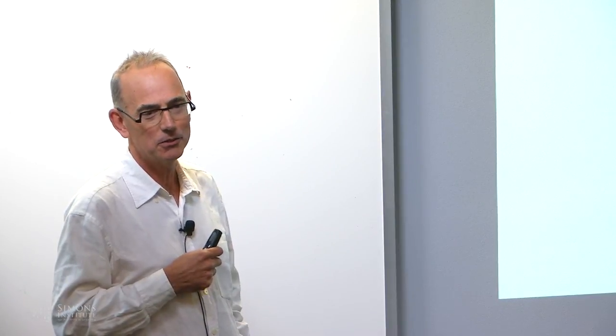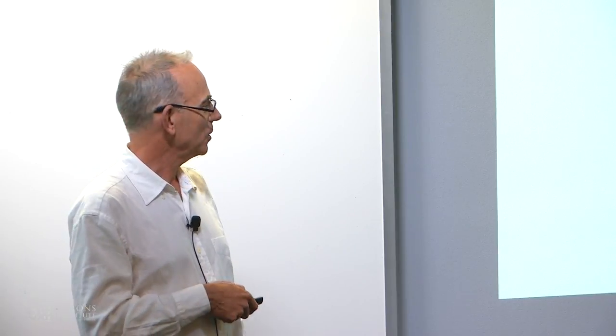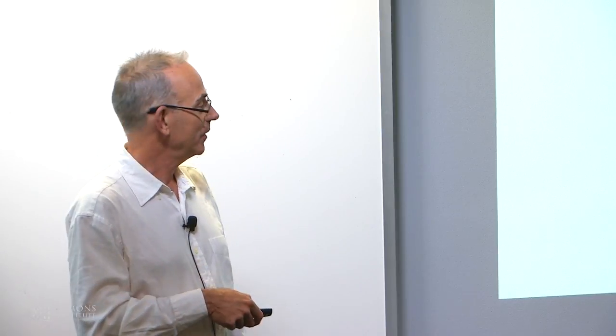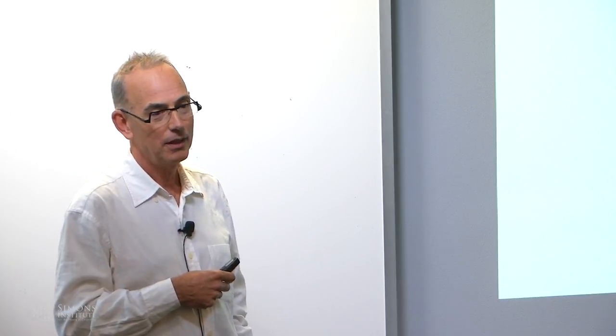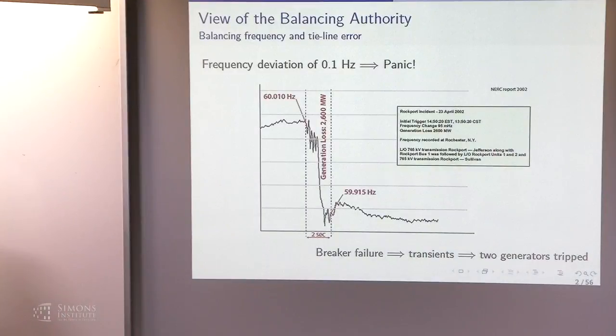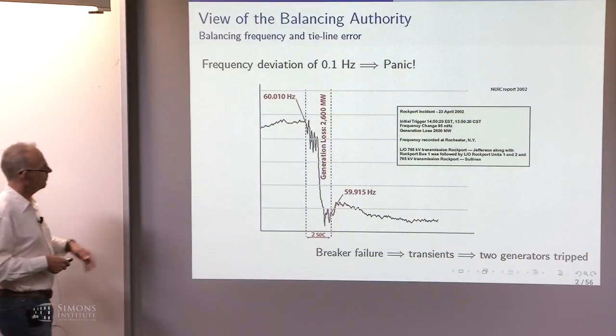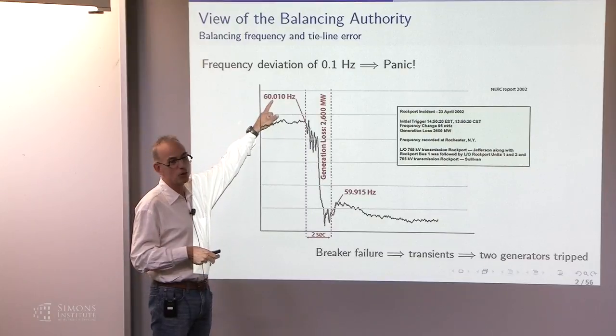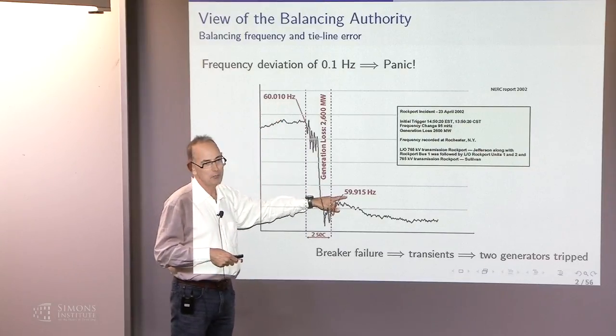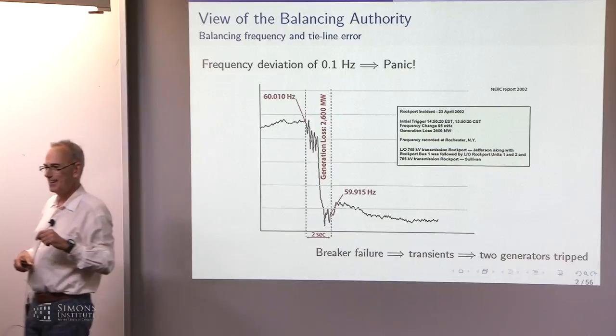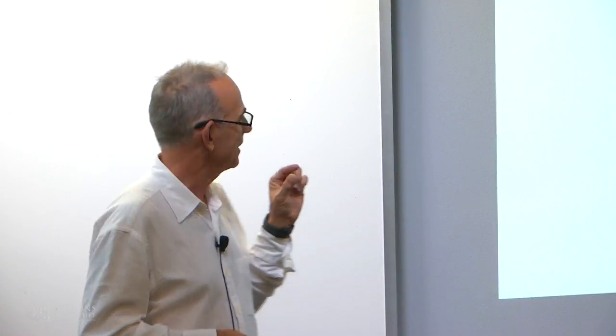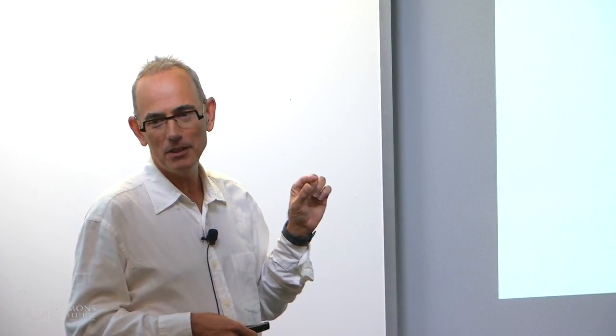It happened because first a circuit breaker tripped, you saw circuit breakers in Stephen Lowe's talk, and that caused some oscillations and transients, which then caused two massive generators to trip. Look at this horrible event, stare at it carefully: the frequency went from 60.01 hertz to 59.915 hertz. That kind of tolerance, about 0.1 hertz, is enough to completely cause a panic and could lead to a blackout. This tolerance is incredible.